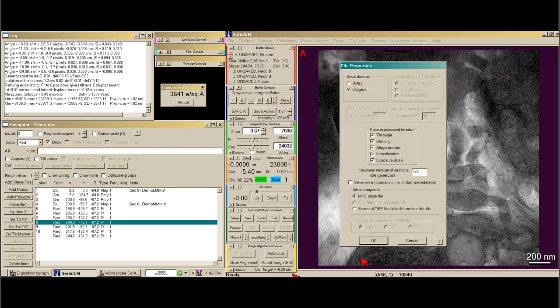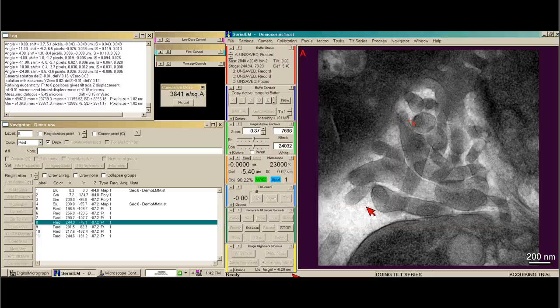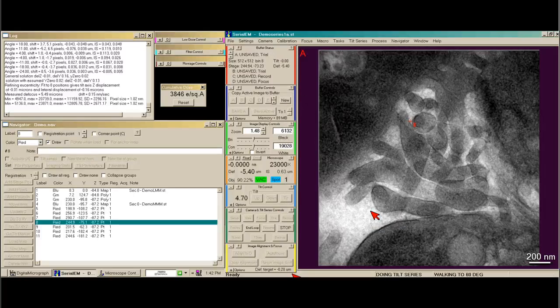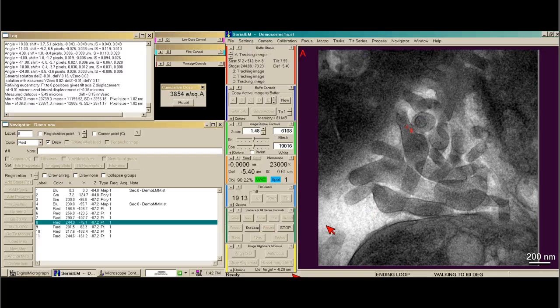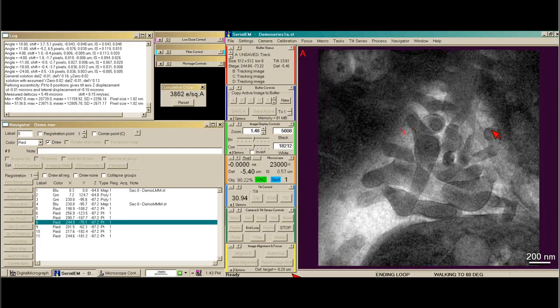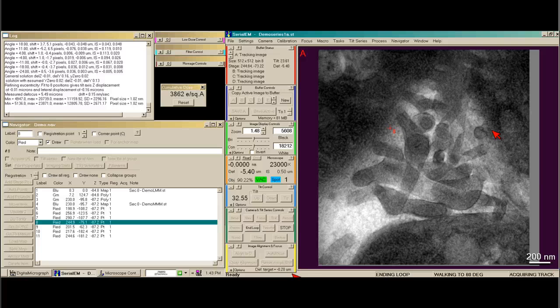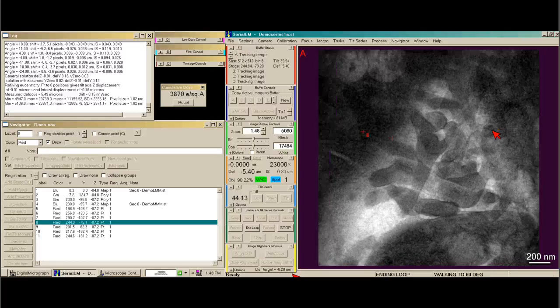We go ahead and say go. I always save everything in the extended header, and this is demo series 1a.st. Save. Now it's going to start walking up to 60 degrees using a series of track images. I always like to say end loop — it tells you at the bottom that it's ending the loop. The reason is simply to double-check my first image and make sure it's not very drifty or that I didn't lose my centering.